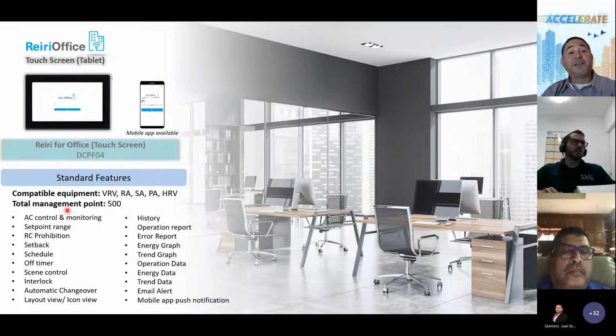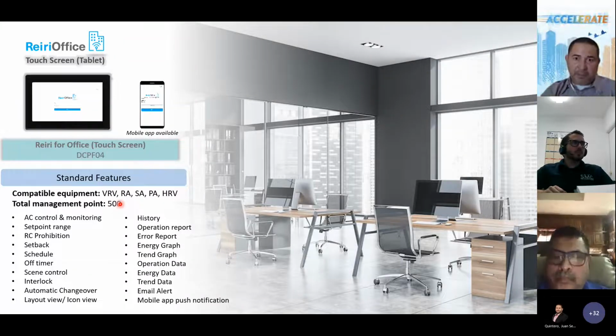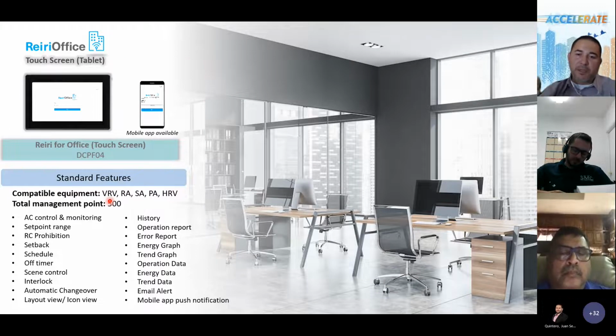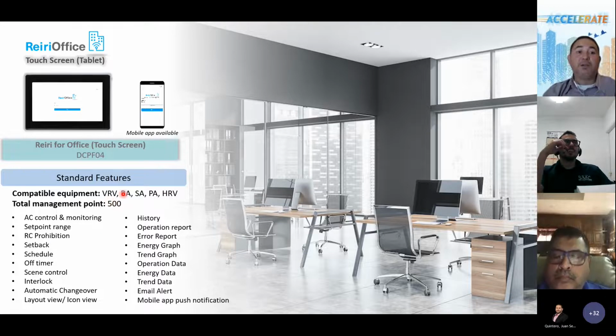Now the total management points are going to be 500 points. Remember, I say this product is for small to medium-sized buildings because of this limitation, 500 management points. What does this mean? If I have an AHU and I want to control discharge temperature, return temperature, the VFD, the fan velocity, and pressure through the filter, I've got four management points that I need to deduct from that 500, right?